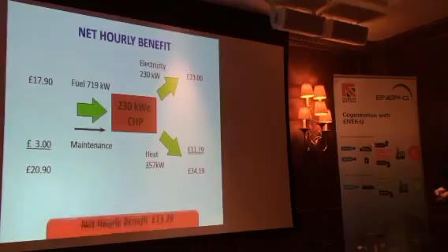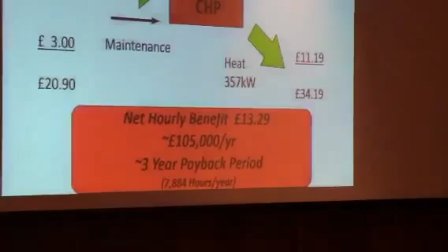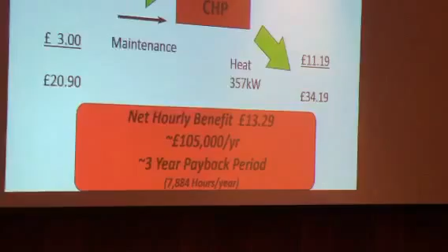So let's draw this together: there are the costs, £20.90, and there are the savings. The real way to look at CHP is the net hourly benefit. Running for one hour at full load, that 230 kilowatt machine downstairs earns £13. Now, £13 doesn't sound like a lot, but that's only for one hour.